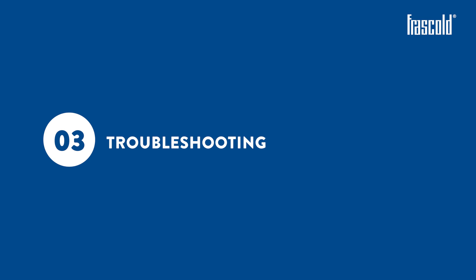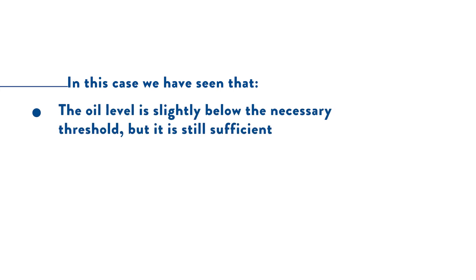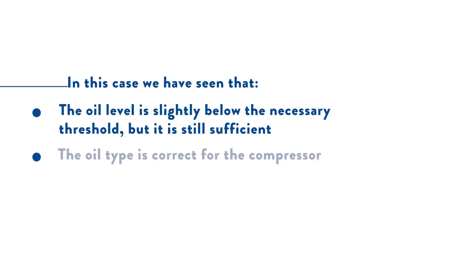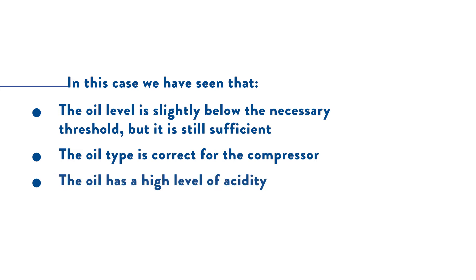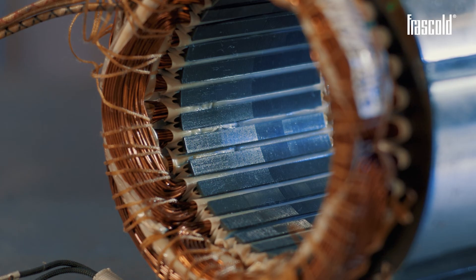Troubleshooting: the results of the two previous tests show us that the oil level is slightly below the necessary threshold, but it is still sufficient. The oil type is correct for the compressor. The oil has a high level of acidity. This leads to the following problems.